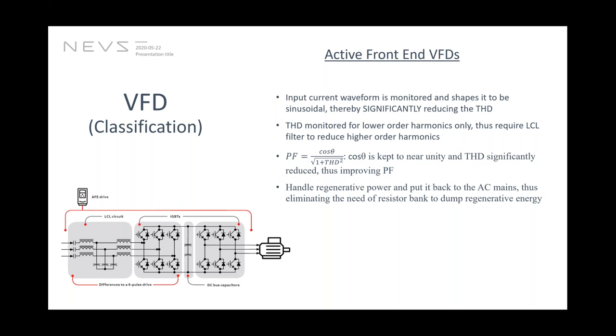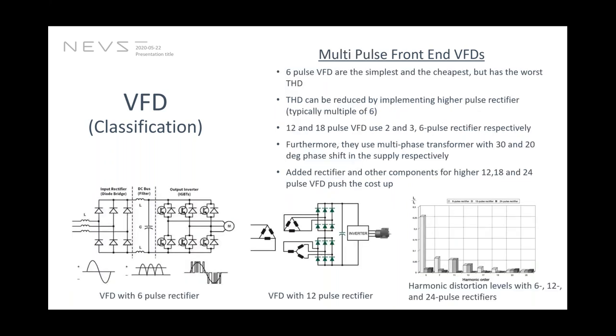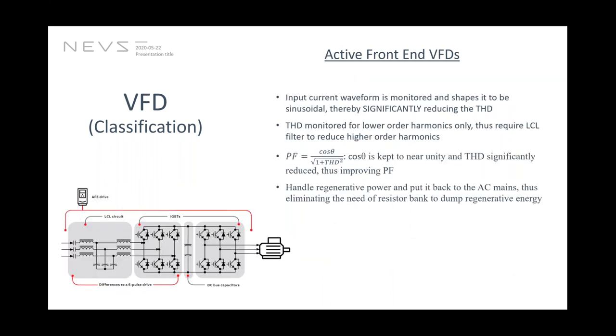So if there is any regenerative power being produced by the motor, you can always put it back to the AC mains or the grid, which again usually will eliminate the need for a resistor bank to dump that regenerative energy. So these are the advantages of active front end VFDs, and comparing the cost, if you need to comply with the grid requirement, probably a 6 pulse VFD won't be so good. Then to comply, either you have to use a filter or active power factor correction or whatever it is, or you have to go to 12 and 18 pulse VFDs, which in both cases will increase the cost. In that case, it might be justifiable to use the active front end.